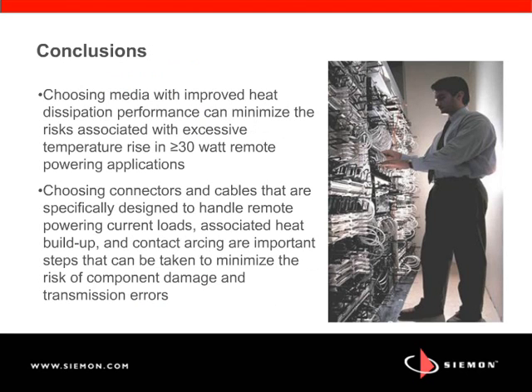The second takeaway is to understand that there are cabling products that are designed to operate under the demanding remote powering conditions, and these products are available today. These include choosing cables that have improved heat dissipation properties, and finally, point 3, choosing connectors that are designed to handle the contact arcing potential during a mating under load condition.